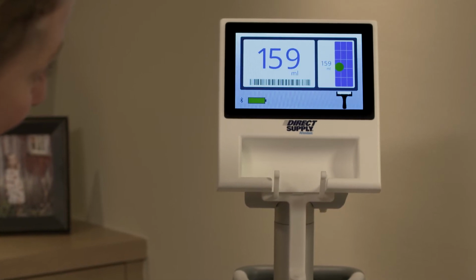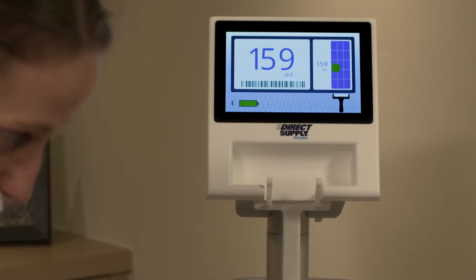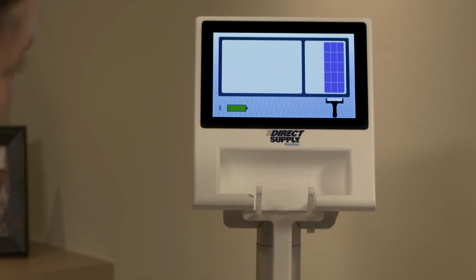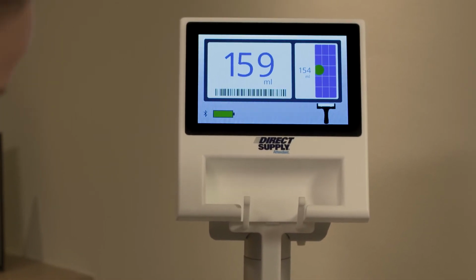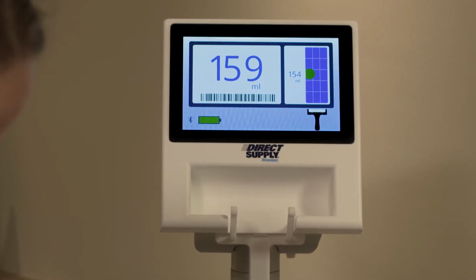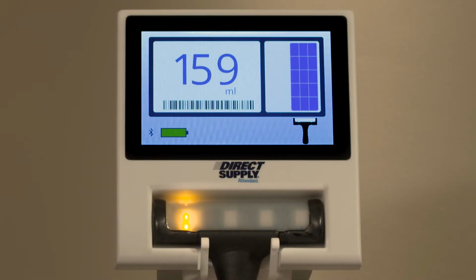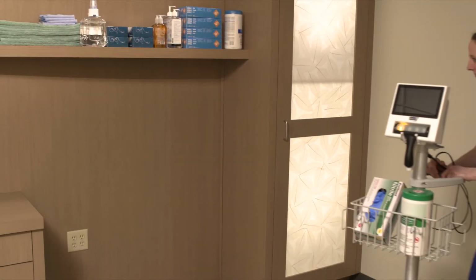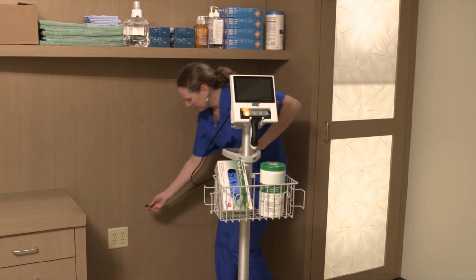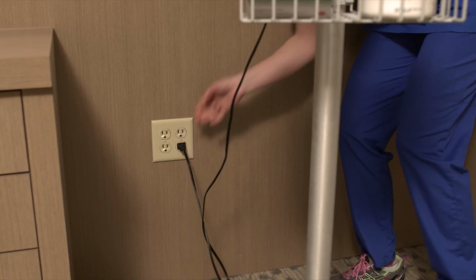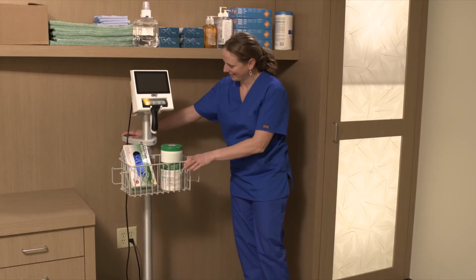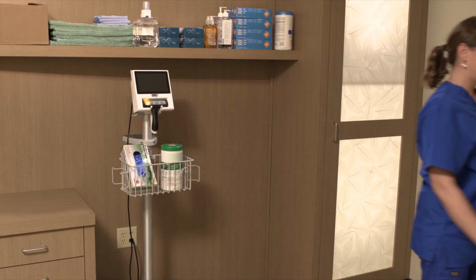The current reading and bladder projection will be cleared from the screen. The largest and most accurate reading from the session will remain displayed on the left side of the screen. Be sure you document the result. The value will be displayed for 30 minutes after the scanner probe is returned. Then, yellow lights will appear on the scanner probe, indicating that it is charging. At the end of the day, return the unit to its storage or charging location and plug it in so it can charge and perform self-diagnostics and calibration.